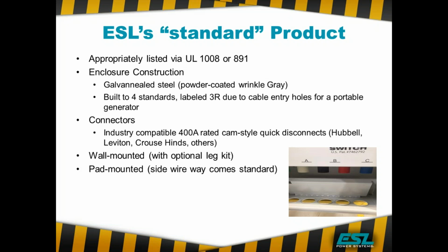Depending on which type of unit it is, it's either 800 amps or 1600 amps that determines when they become pad mounted. If you have a wall mounted application where you're not going to mount it to a wall, it's going to be remote. We can provide the optional leg kit. Typically in those situations, a lot of times the contractor is building his own trestle because he's also going to mount a disconnect or a meter or something else, and we'll just fit on the same one. But in those instances where that's not going to happen, we can supply a leg kit.